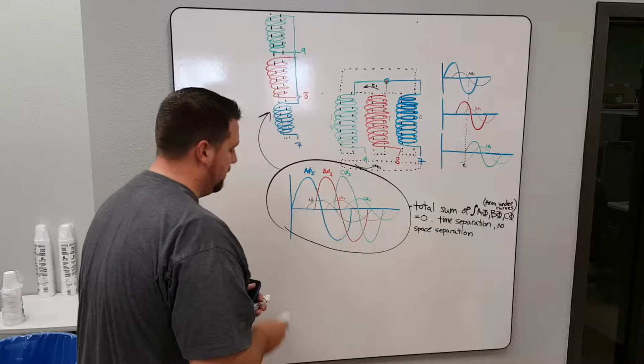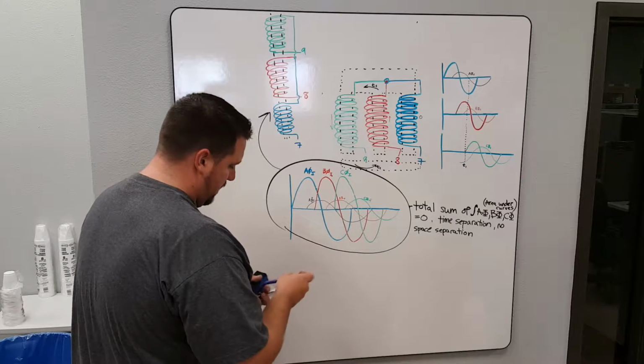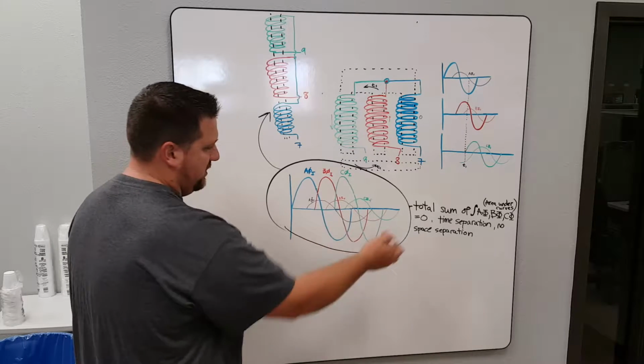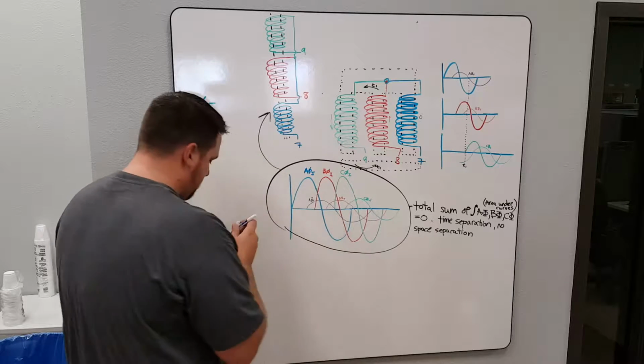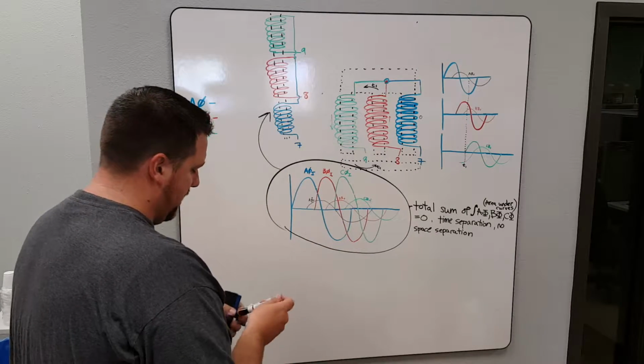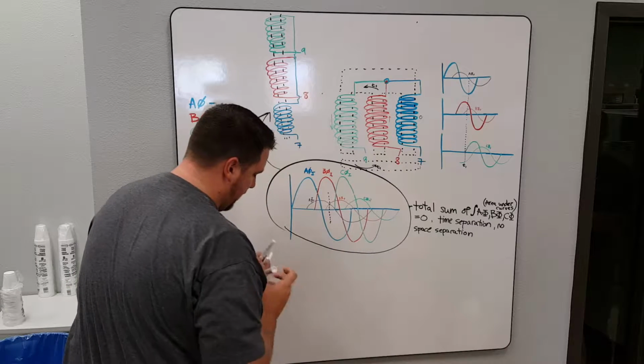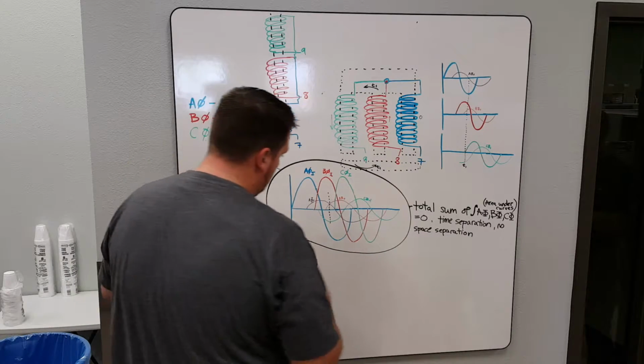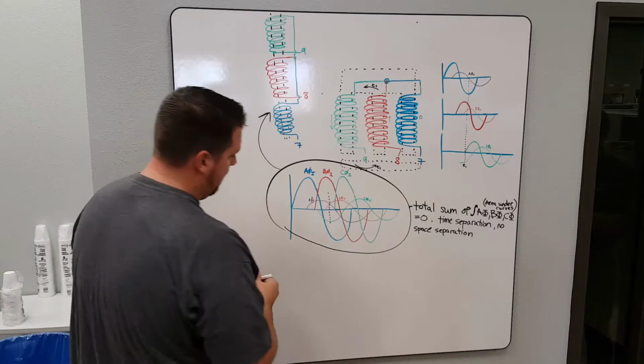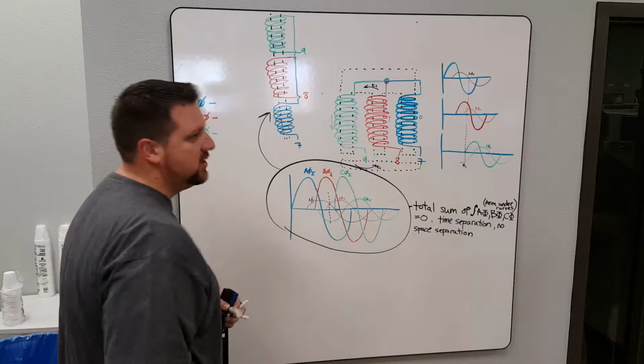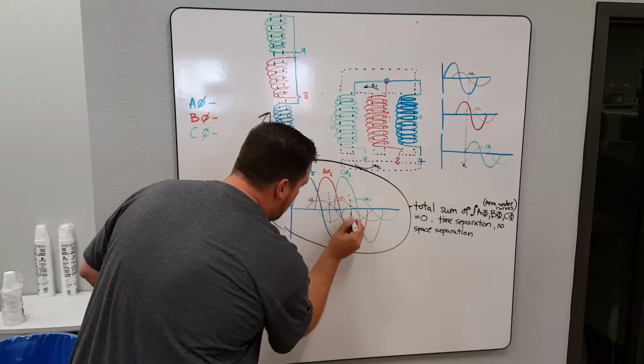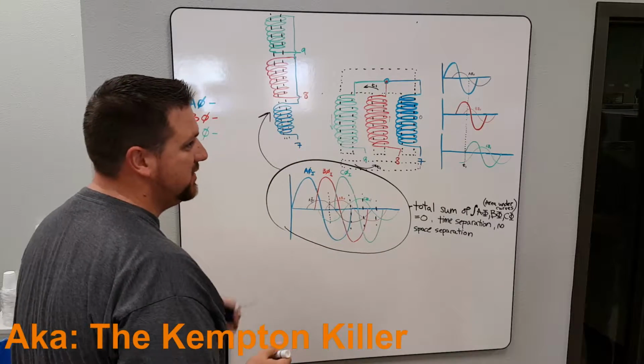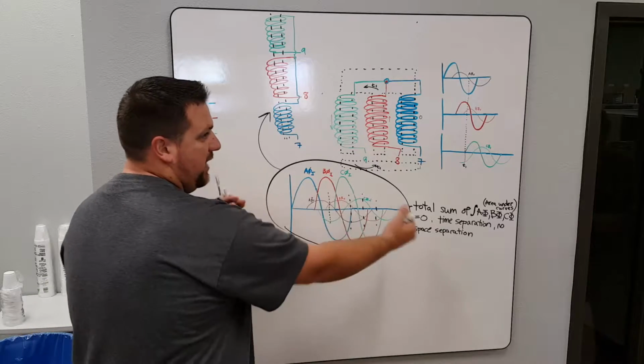What's going to end up happening is we take the area under the curve, which pretty much is the integral. Let's try to break it down a little simpler than that. Let's say I wanted to measure the flux in the core at one specific time. I'm going to take my black marker here and say at time 1, I add up the total amount of flux within the core. Can anybody tell me what this plus this plus this is going to be? It's going to be 0. If I take that same time stamp anywhere and add them up, it's going to be 0, because the amount of flux is going to be the same any place, and it's going to equal 0.